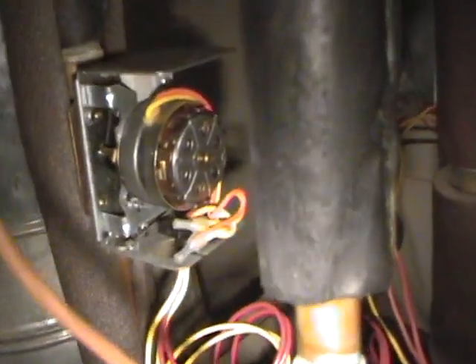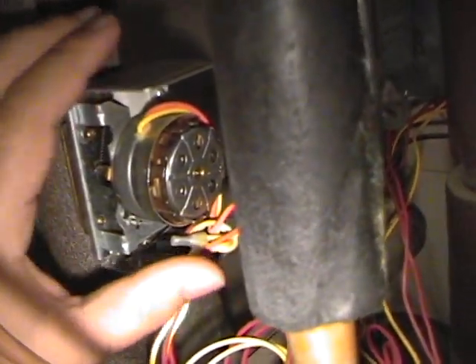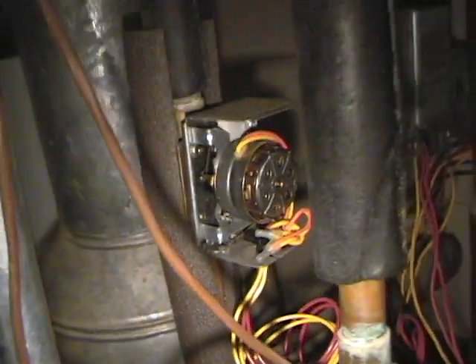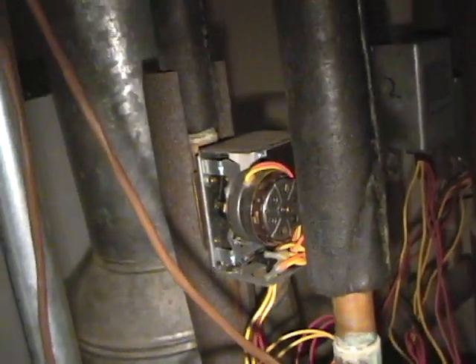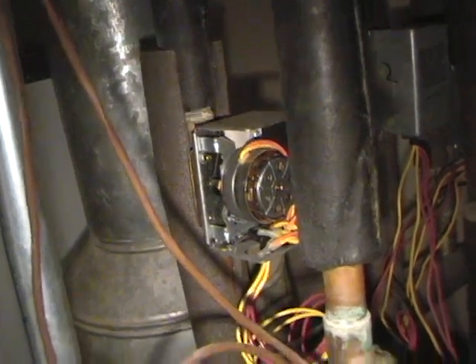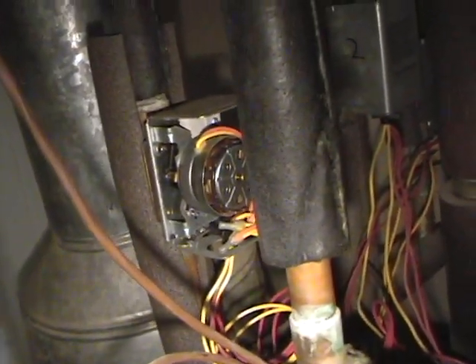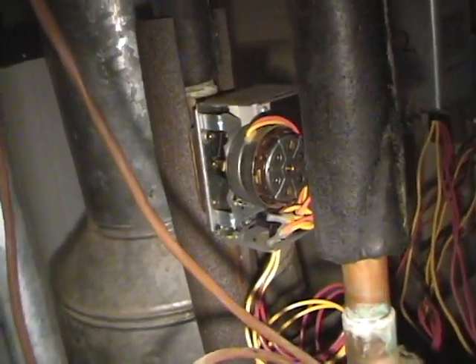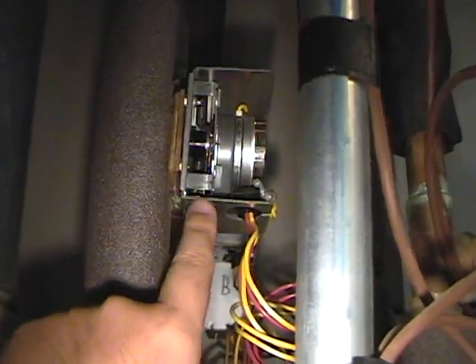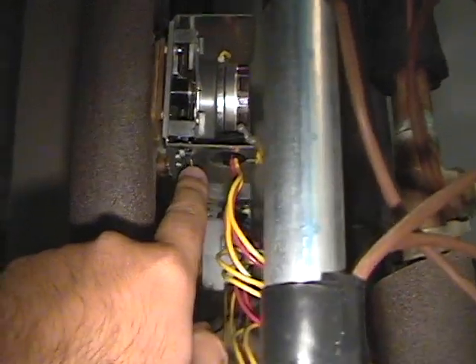So it's a very interesting process as to how all the thermostat does is just control this piece right here. Now, let's say by chance that your valve malfunctions, or maybe your thermostat malfunctions and you need to get heat. There's actually an override switch down here, or kind of lever right there. You see that? And you can push that open, and then that will actually open the valve.